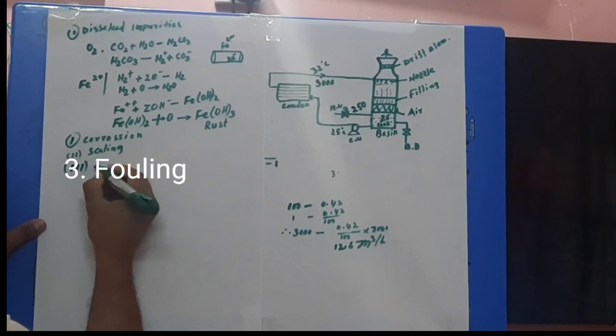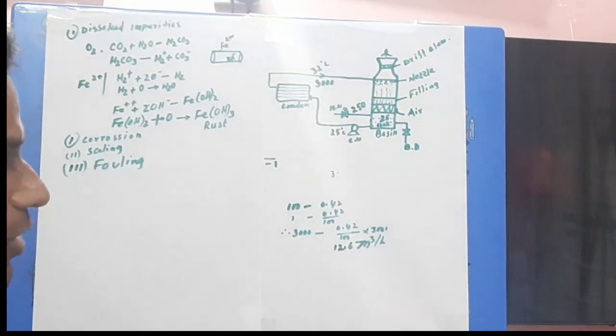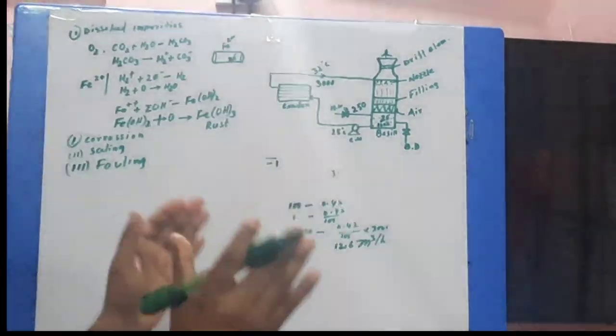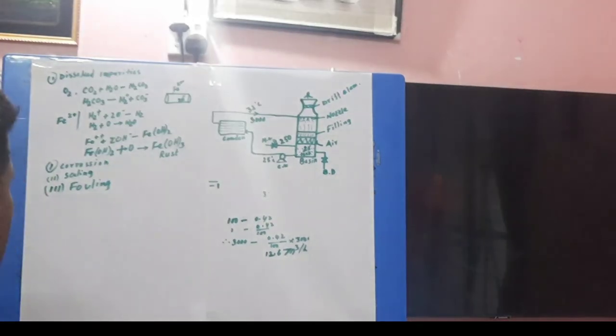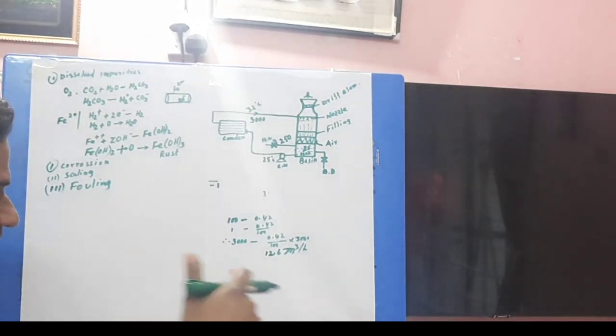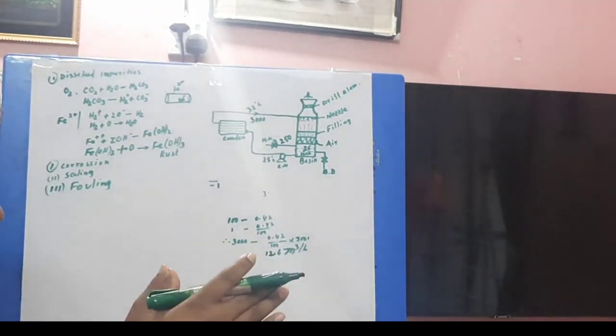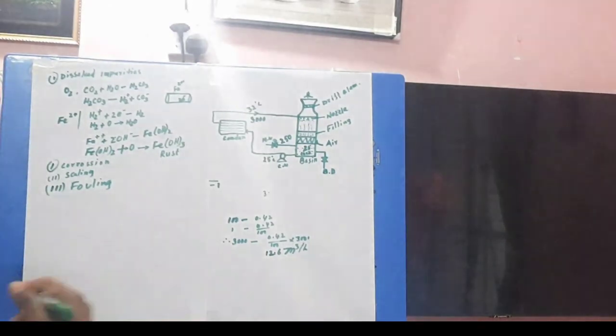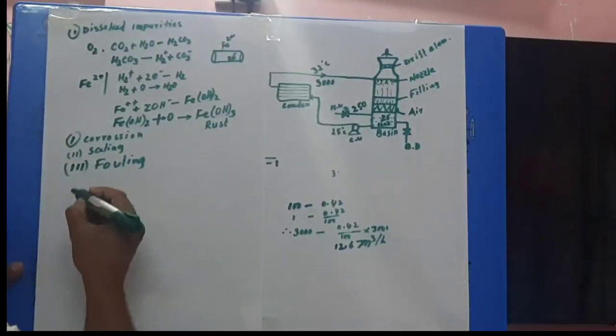The third problem is fouling. If suspended solids are present in the water, they go to the condenser and create fouling. To control fouling, you have to provide a dispersion solution. When you provide the dispersion solution, the surface charge increases. If surface charge increases, the particles maintain distance from each other and do not accumulate on the tube.